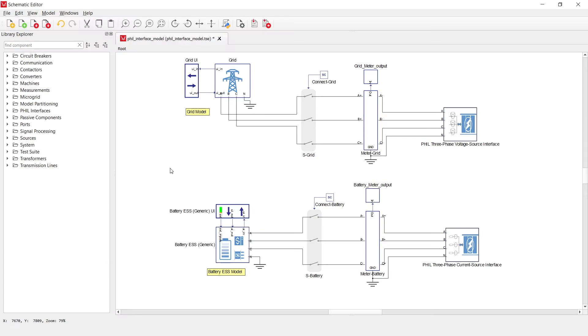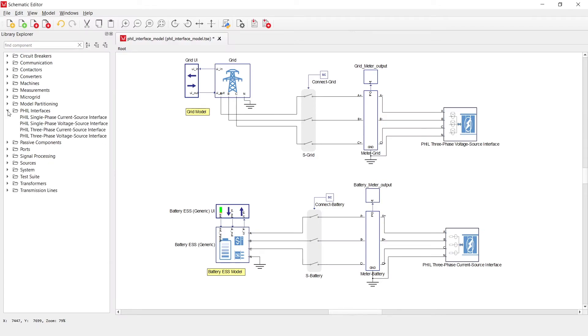PHIL interface components can be found in the specially dedicated PHIL library. Here we have four components — two of them are single phase while the other two are three phase. There are two types of PHIL interface components: voltage source type, which is used with amplifiers operating in voltage control mode such as grid emulators, and current source type, which is used with amplifiers operating in current control mode, for example load emulators.